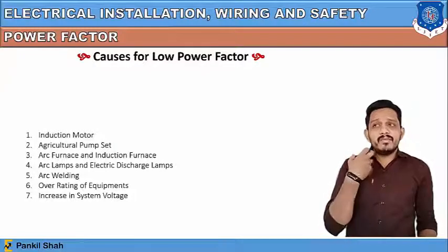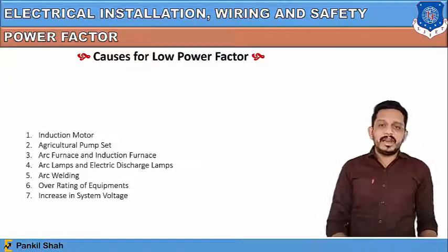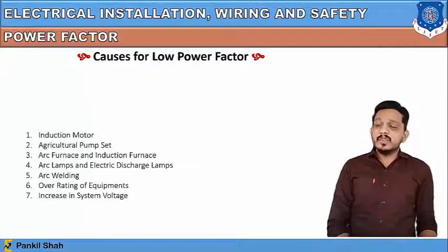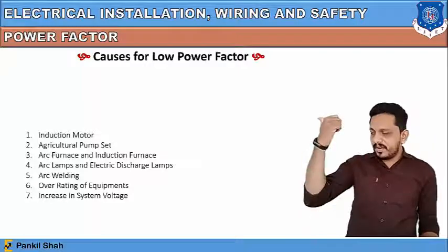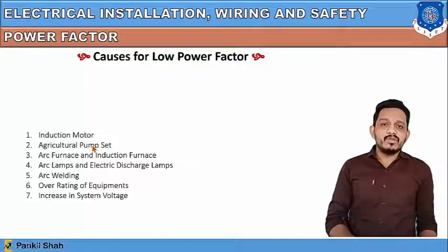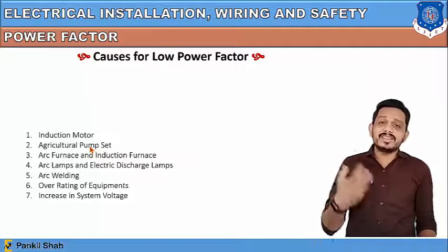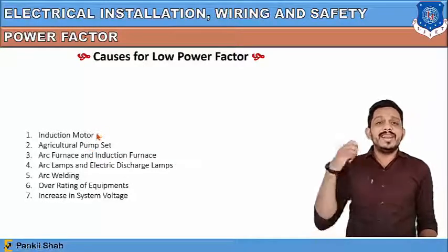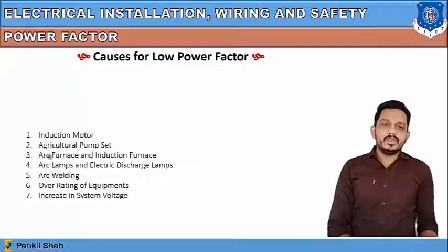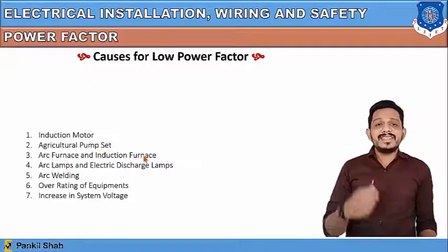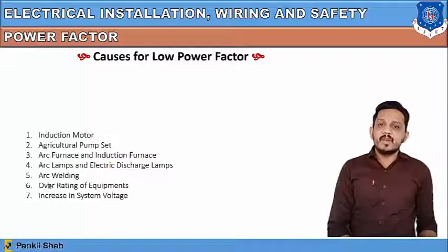Someone might have a question: how does the system end up with a low power factor? The reasons behind the low power factor are as follows. If you are using an induction motor, the system will obviously have a low power factor, and we use induction motors in every industrial application. Agricultural pump sets will also cause a low power factor. Arc furnaces and induction furnaces also cause a low power factor.